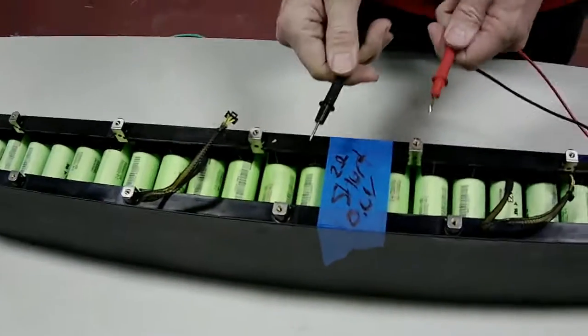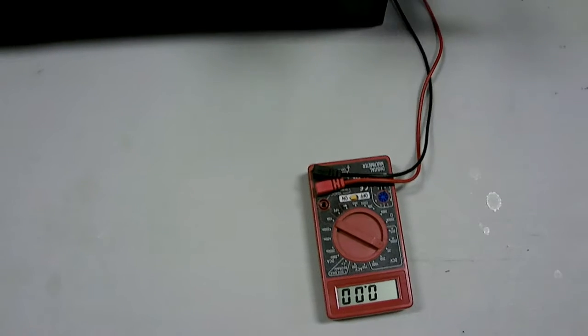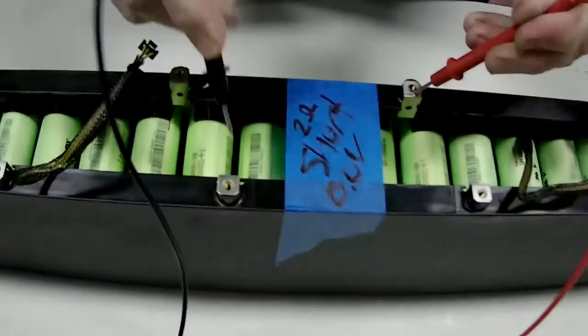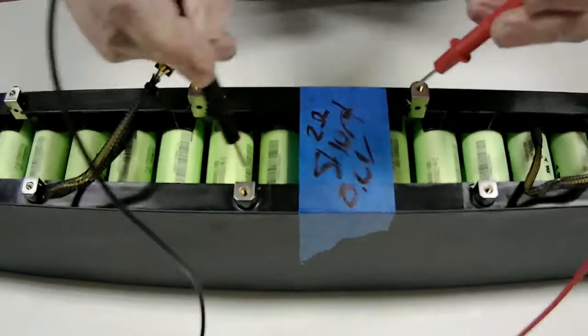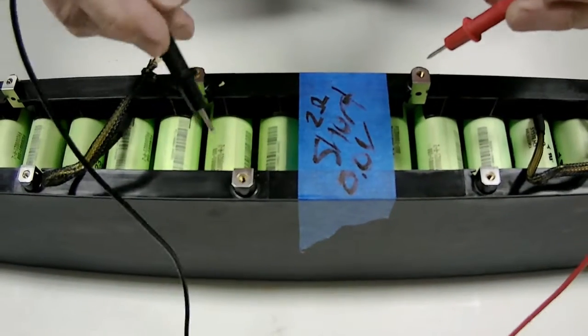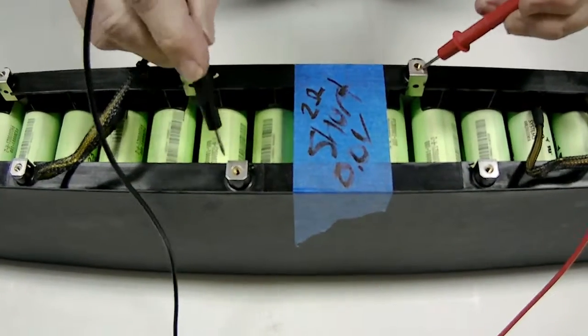We don't know. Now, I want to know, is this an open circuit or a short circuit? The meter, as a voltmeter alone, can't tell an open circuit from a short circuit. Either way, it's the same voltage difference. So I switched to ohm meter mode. We've already verified that there's 0 volts across it. Now measuring carefully across just this pack. Don't do this on any other high voltage or any circuit with voltage on it. If you put a higher voltage across it from the battery, a lot of current will flow through the meter and the meter will quit working.